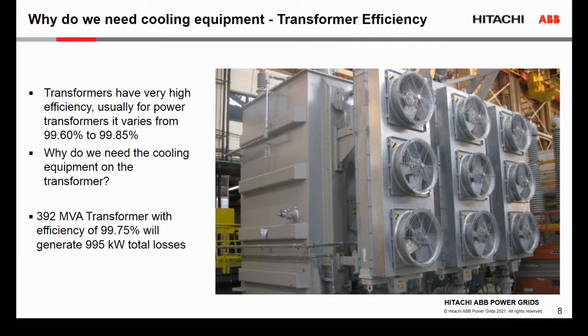First, why do we need the cooling equipment on the transformer? A power transformer is a very efficient electrical apparatus. The efficiency of a large transformer is 99.6 to 99.85%, so why do we need the cooling? For example, take a generator step-up transformer, 392 MVA with an efficiency of 99.75%. We have almost 1,000 kilowatts of losses in the core and in the winding. This type of losses will increase the temperature inside the transformer quickly, within a few minutes or even sooner than that.